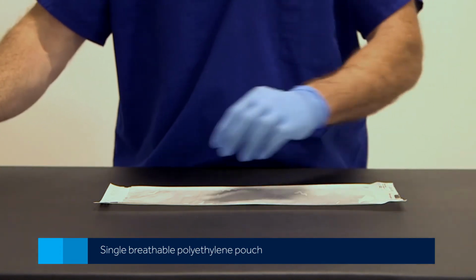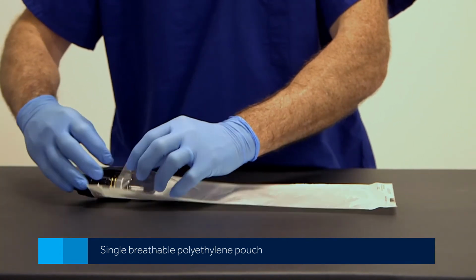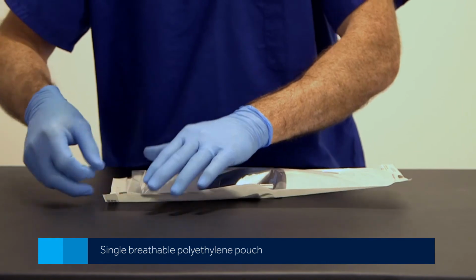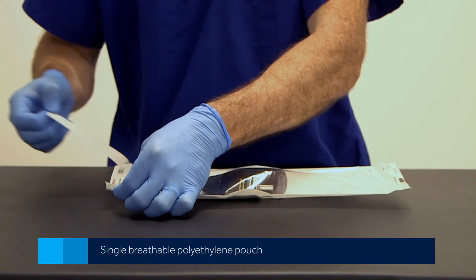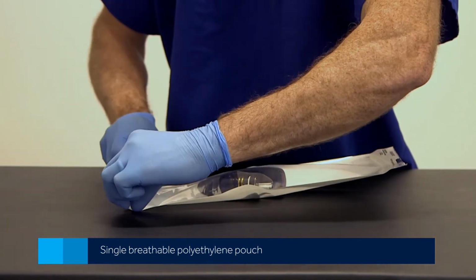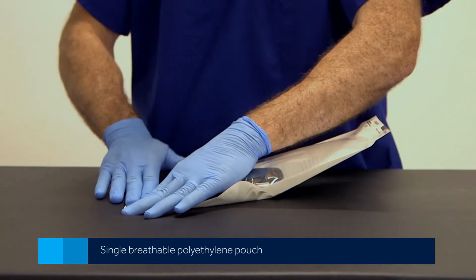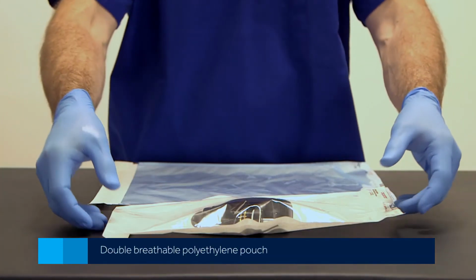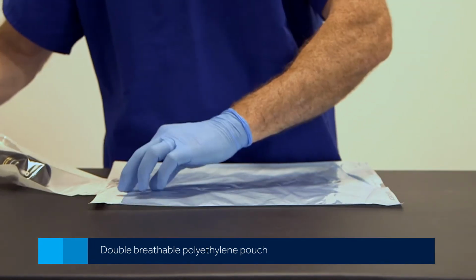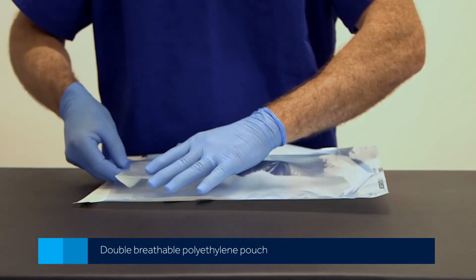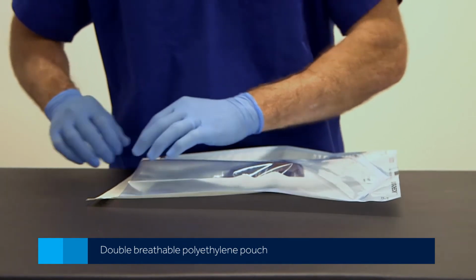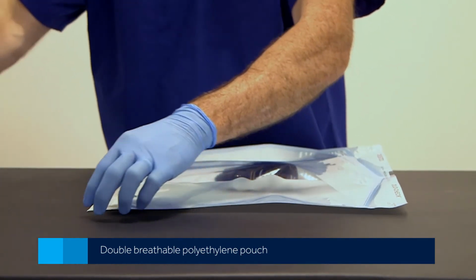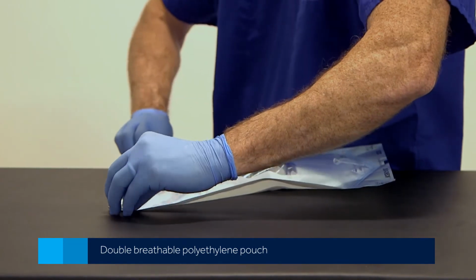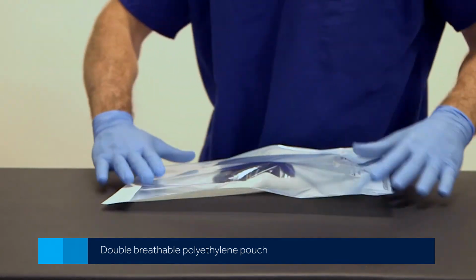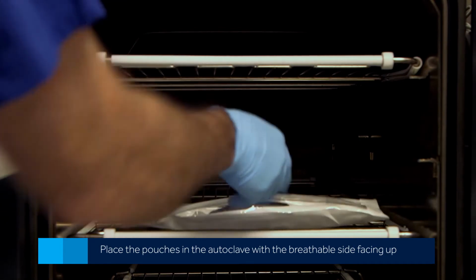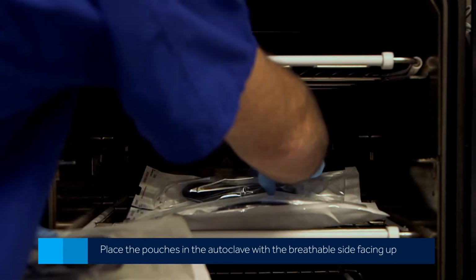For a single breathable polyethylene pouch, place each component individually in its own single compatible breathable polyethylene pouch and seal. Place the pouch in the autoclave with the breathable side of the pouch facing up. For a double breathable polyethylene pouch, place each component individually within 2 compatible breathable polyethylene pouches and seal. The breathable side of the inside pouch must be aligned with the breathable side of the outside pouch. Place the pouches in the autoclave with the breathable sides of the pouches facing up.